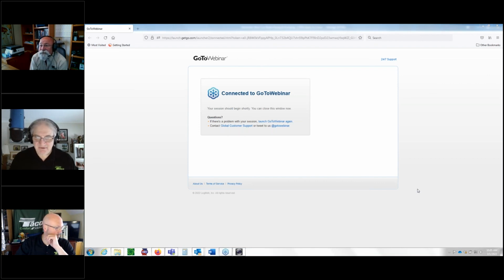And this one just came in from William Sherwin. It appears that using a variable speed primary pump that allows for setting up the flow by delta T versus old-fashioned flow measurement, the cost and time is much less, and the increase in accuracy is worth the extra initial cost of the pump. Yes, that's a statement we've been making for, oh boy, how long? I'd say almost 10 years now. Delta T pumping is by far and away the most accurate and best way to run any hydronic system.